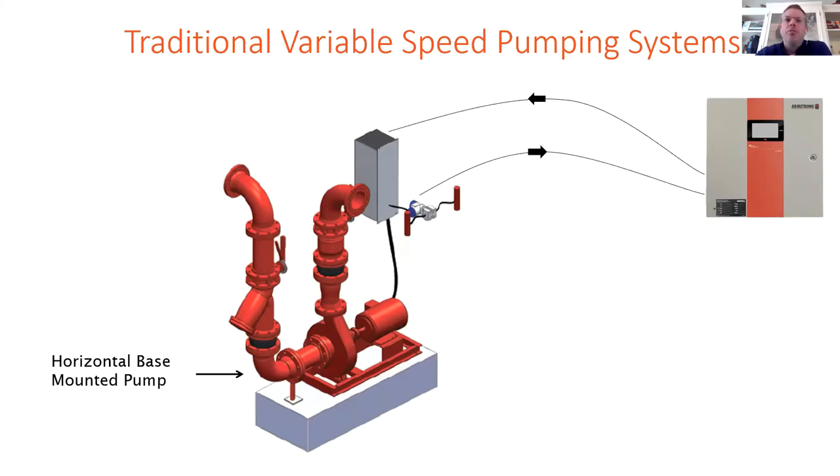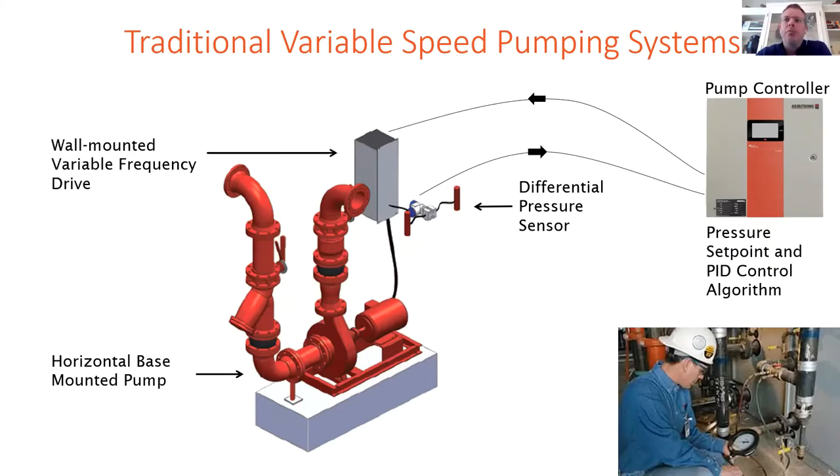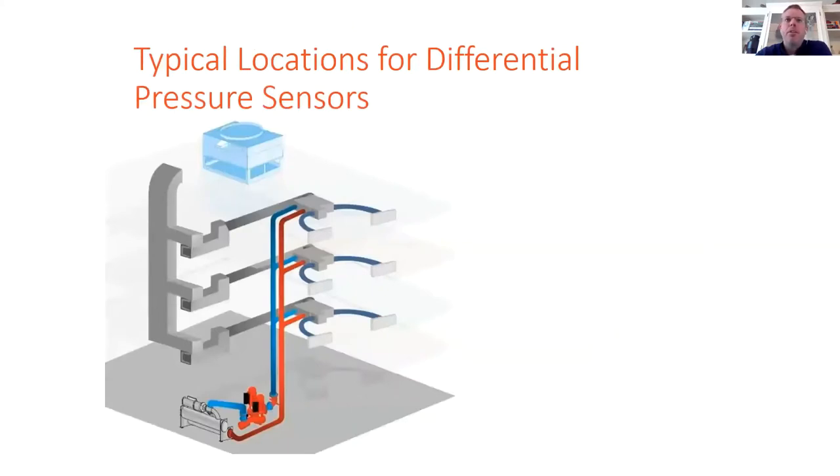With a traditional variable speed pumping system, there's a differential pressure sensor that's located out in the system somewhere. And via a test and balance contractor, a minimum pressure set point is determined which will satisfy the most remote load during normal operation. The pump controller is then going to vary the speed of the pump motor via variable frequency drive to ensure that the differential pressure set point is maintained as two-way valves open and close out of the system.